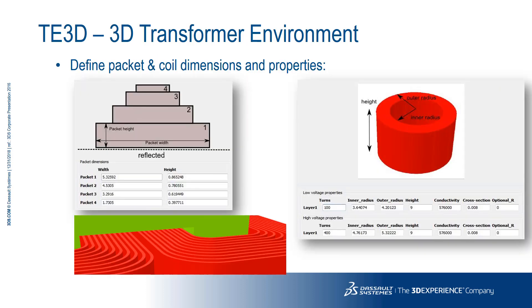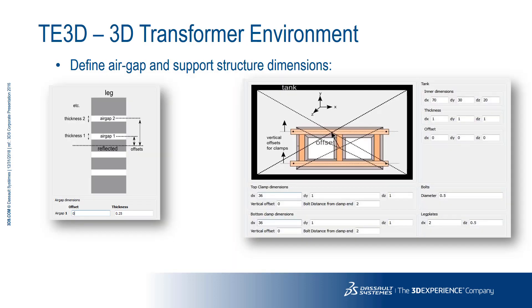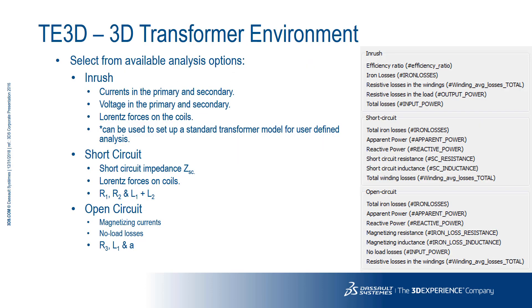Once you've chosen the basic topology, you are presented with a series of dialogues to enter the geometrical information, both for the legs of the transformer and for the coils. You can choose by default from solenoids and racetracks and can split them automatically into a number of sub-windings. If you choose to include air gaps and support structure, you'll be presented with dialogues for those components as well — it's easy to generate a number of air gaps in the legs if you're investigating their effect in a new design. Once you have a representation of the device, you select which test you'd like to perform: the default options are open circuit, short circuit, and inrush — the three tests mentioned earlier. Each test will generate the appropriate circuit definition and drive the transformer as per the real-world test.